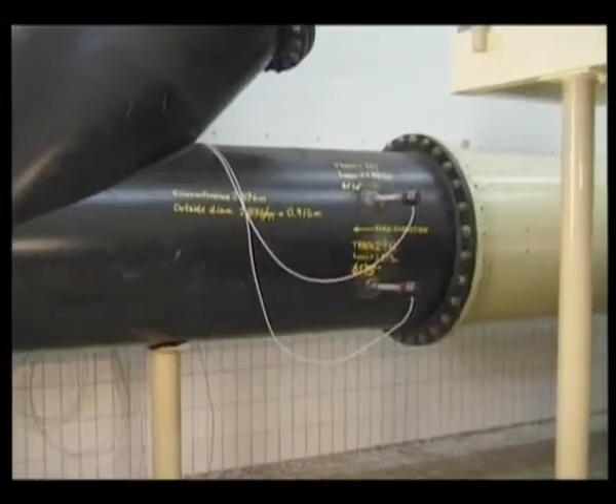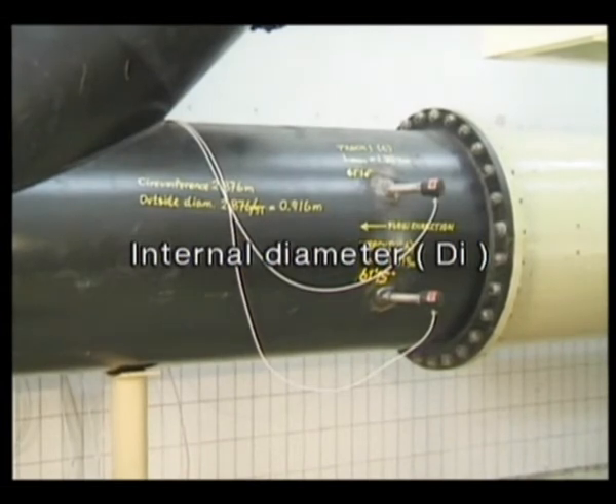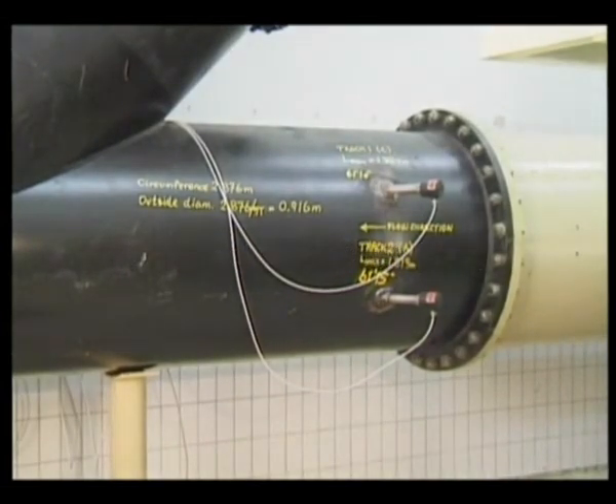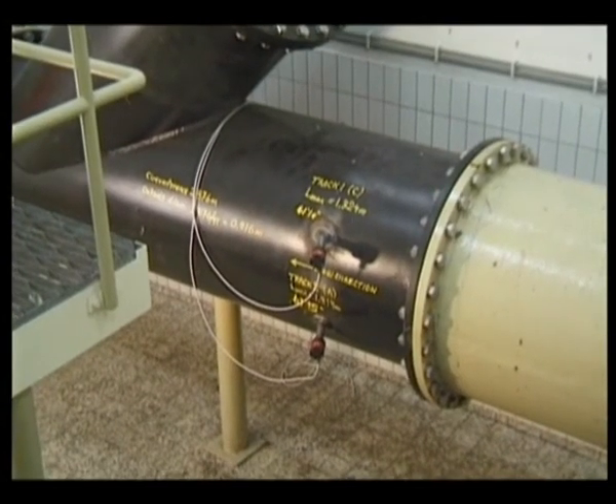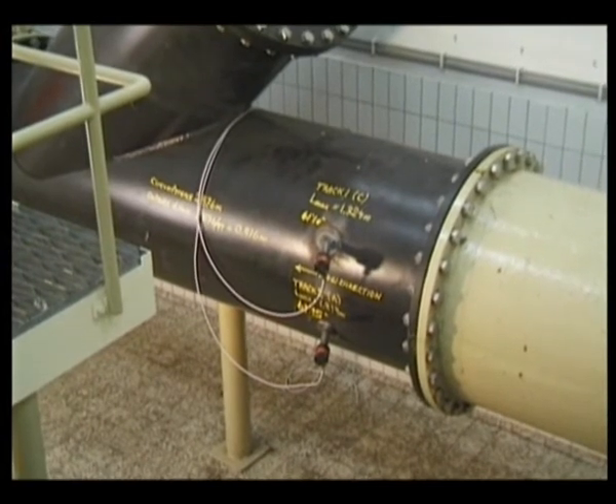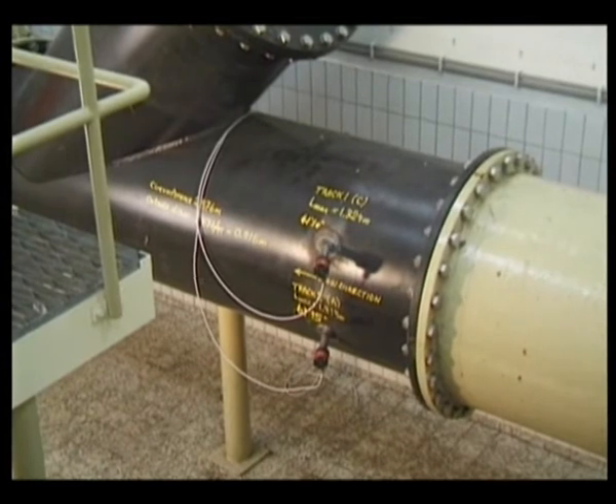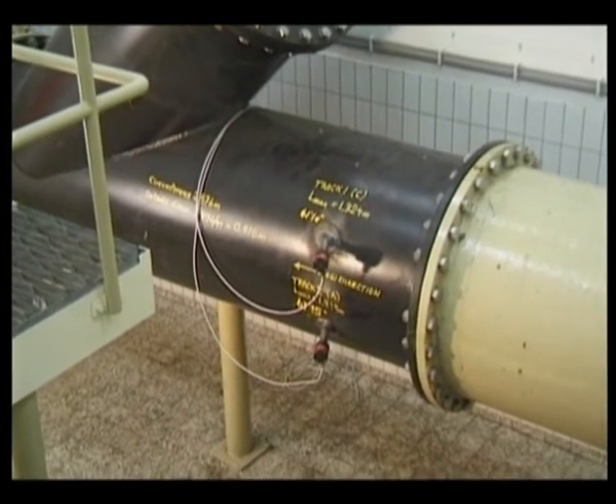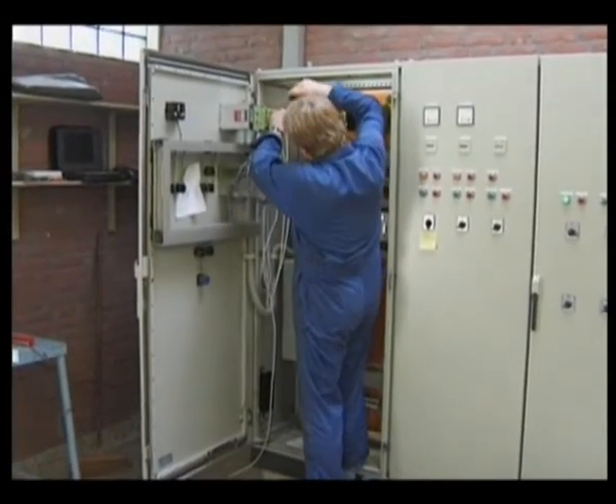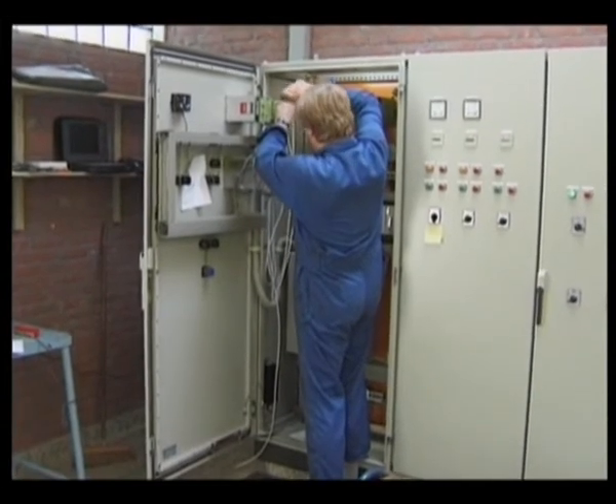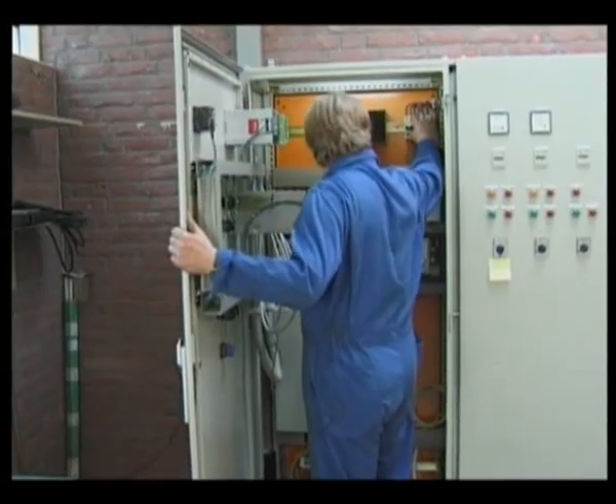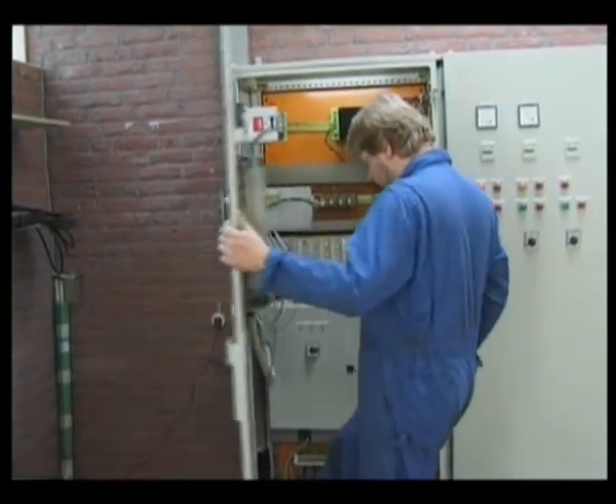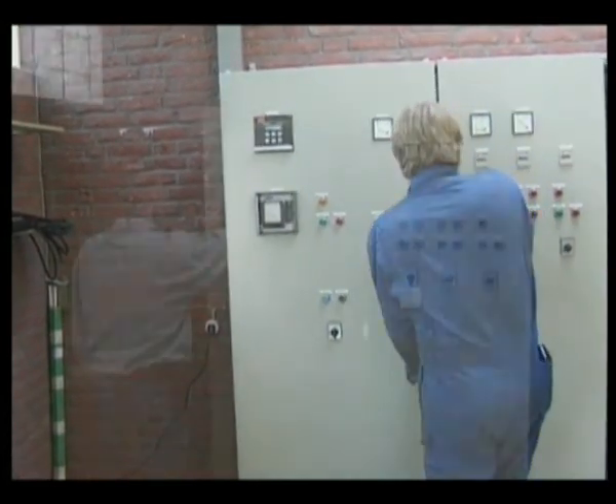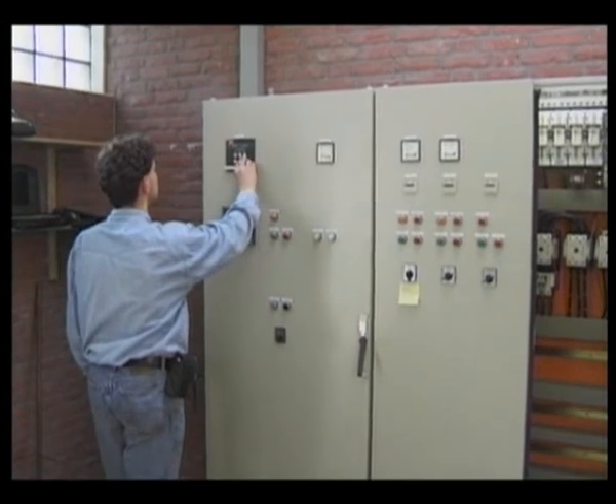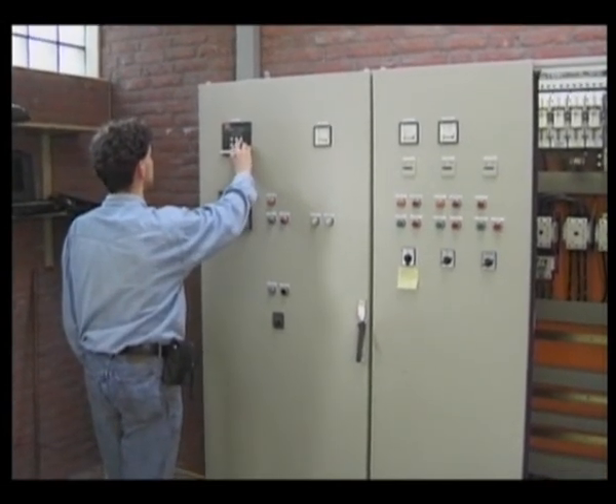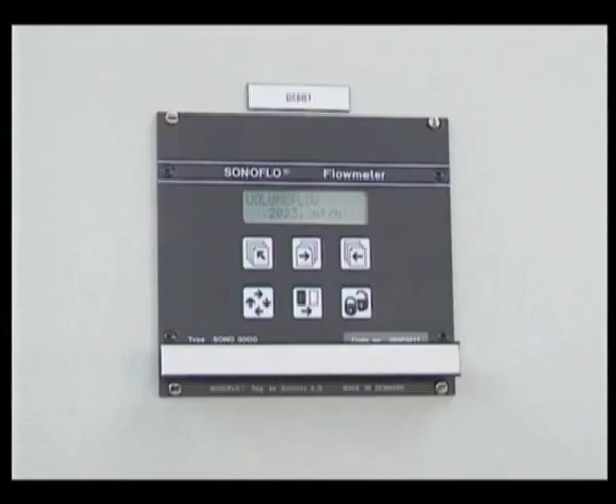The internal diameter is calculated from the circumference and the measured pipe wall thickness. If there's an internal layer in the pipe, this must also be included. Signal cables and power supply are connected to the signal converter. Finally, data must be entered into the signal converter. These data are, among others, the sensor geometry data, which can be read in the measurement report, and the flow rate. The measuring system is now ready for operation.